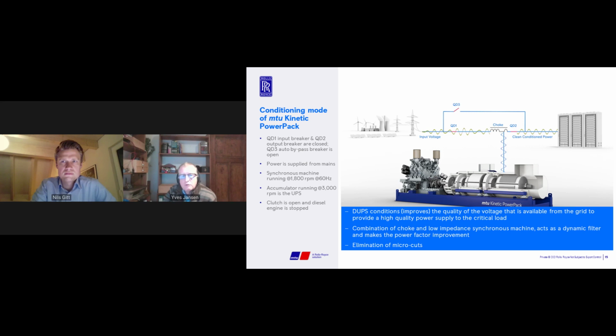In conditioning mode, QD1 input breaker and QD2 output breaker are closed. QD3, the automatic bypass breaker, is open. The active power is supplied from the mains. The synchronous machine is running at 1800 RPM for the 60 cycle application. The accumulator is rotating at 3000 RPM. The clutch is open and the diesel engine is stopped. At this stage, the dynamic UPS improves or conditions the quality of the voltage that is available from the grid to provide a high quality power supply to the critical load. The combination of the choke and the low impedance of the synchronous machine acts as a dynamic filter and makes the power factor improvements.